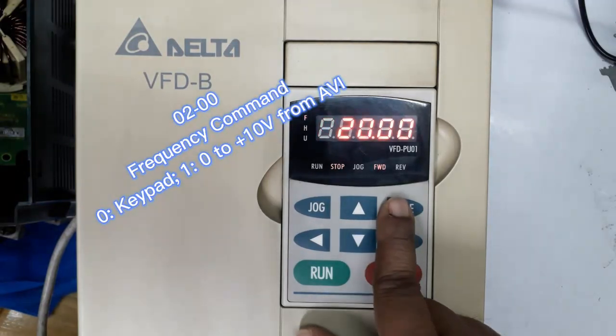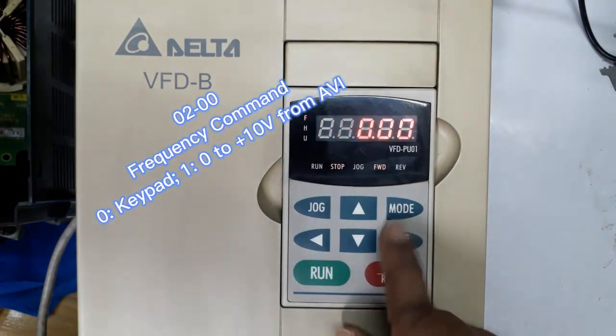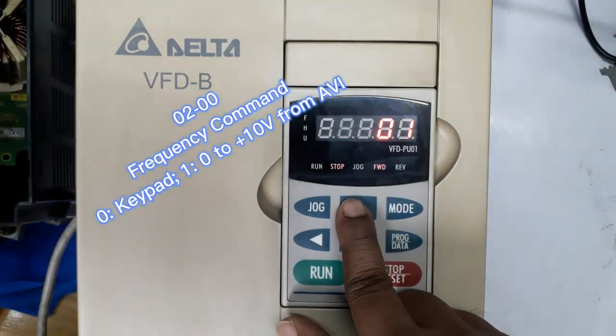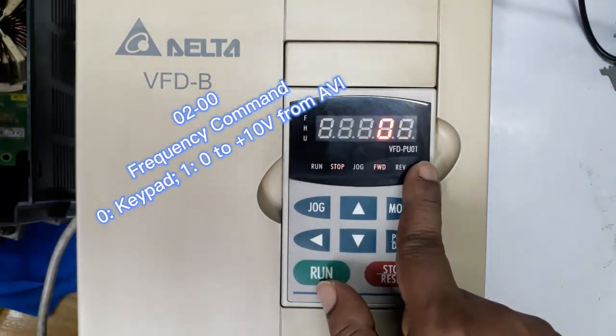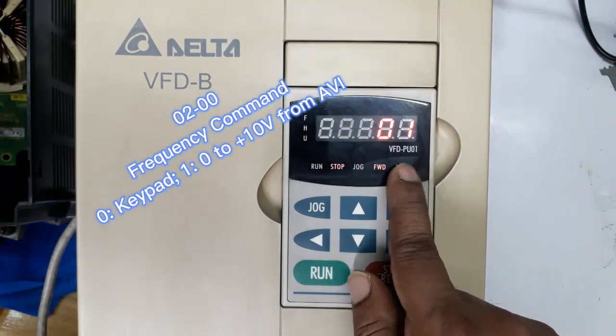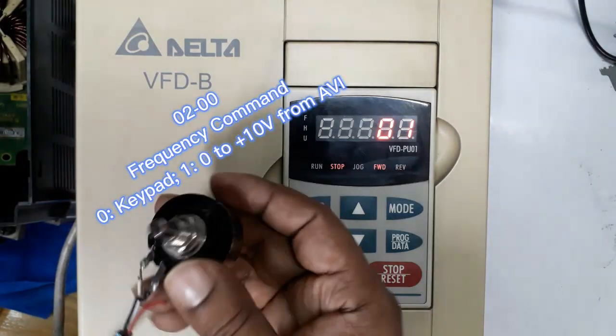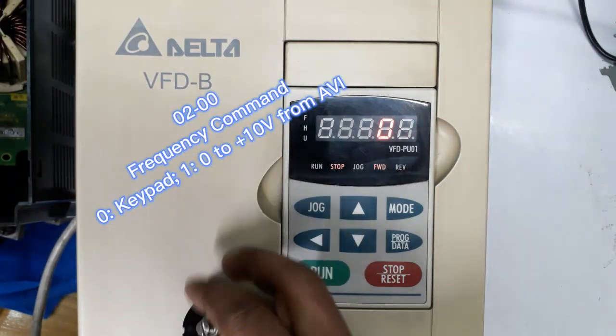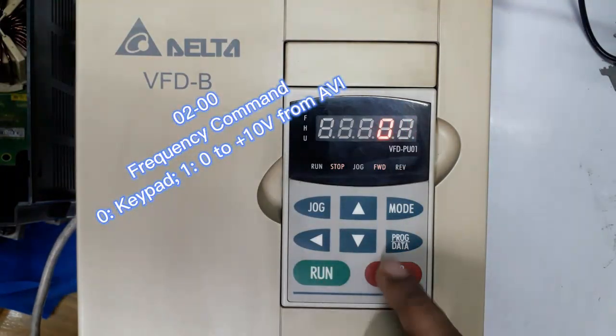But to control externally by terminal run command or terminal frequency command, you can set parameter 2-00. Set here 1 to control by a potentiometer. That means a 0 to 10 volt connection in the AVI terminal. To activate the potentiometer, set here 1.